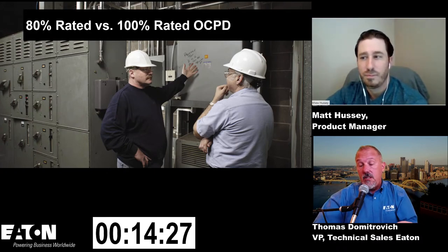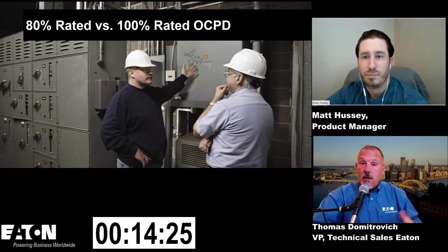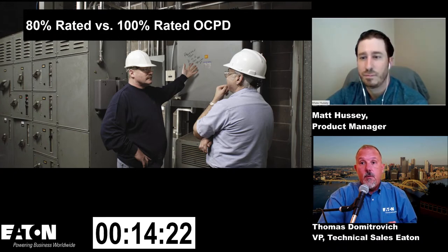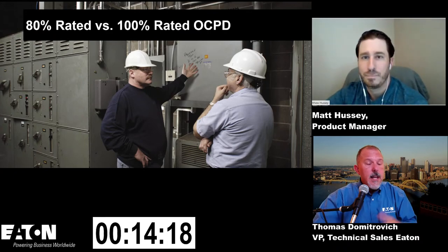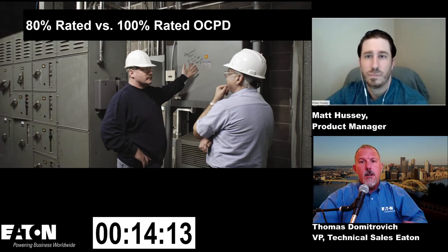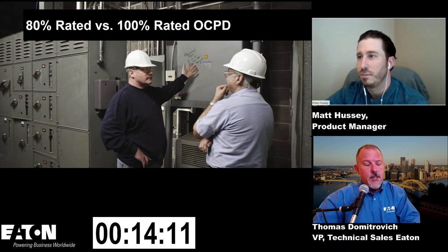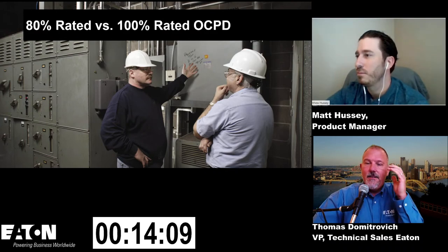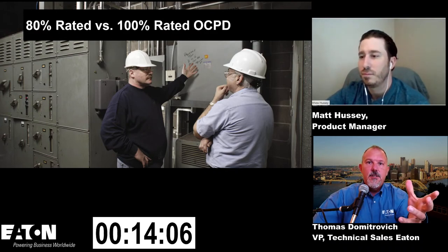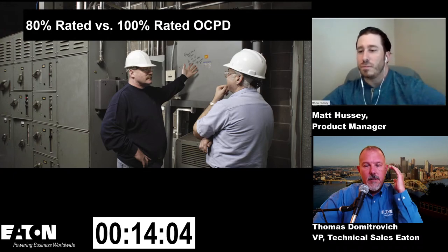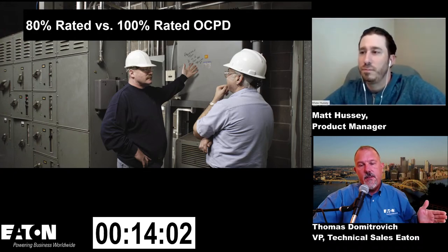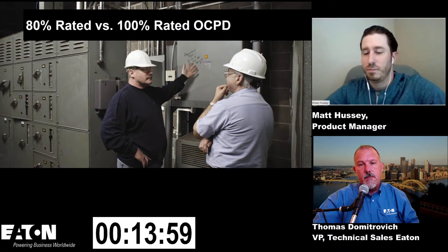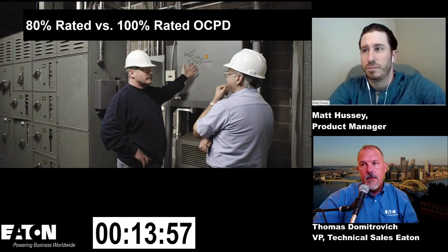And he says, or she says, that we did our calculations for 100% rated equipment or breakers. And how do I fix this? Do I just buy a 100% rated breaker and install it? And they're telling me I can't do that. So I think the challenge is, and what I'm seeing is, when we go down one road, we don't communicate very well, and we have to try to fix something in the field afterwards. That's what I see. I don't know about you, Matt.